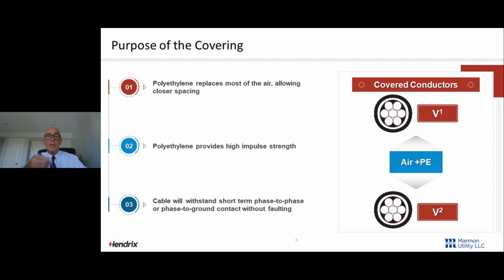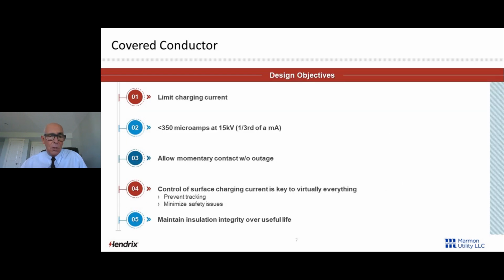So the poly is going to provide a high impulse strength. It's going to provide a high BIL, 60 hertz withstand, and it's going to withstand short-term phase-to-phase contact, phase-to-ground contact, phase-to-animal contact without faulting. So we want to make it much more resilient to the environment in which it's installed.